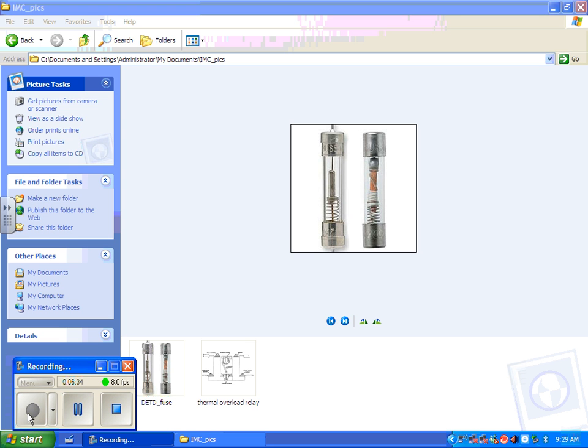Okay, so a solder pot overload is a device that senses the heat, because the solder literally will melt at a very specific point of temperature, right? Very, very narrow band. And we take advantage of that by creating a device that will let a spring-loaded device open up when the solder melts. And that's why it's called a solder pot overload relay. And they're still in use almost everywhere, because they're inexpensive, they're accurate, they're reliable, they're just good at what they do.